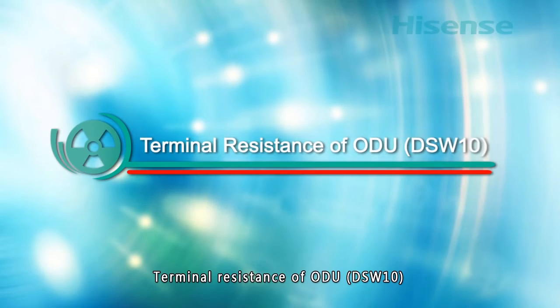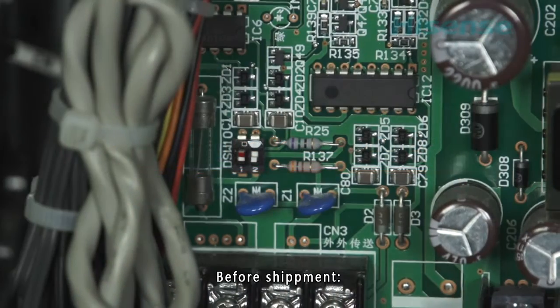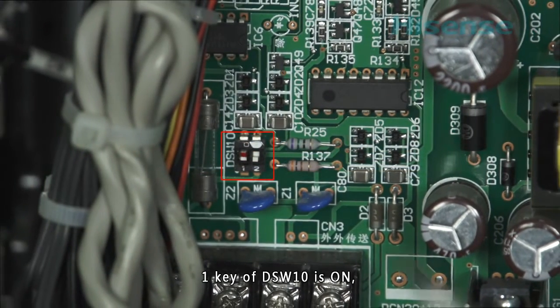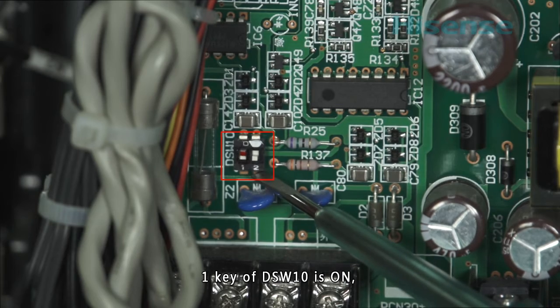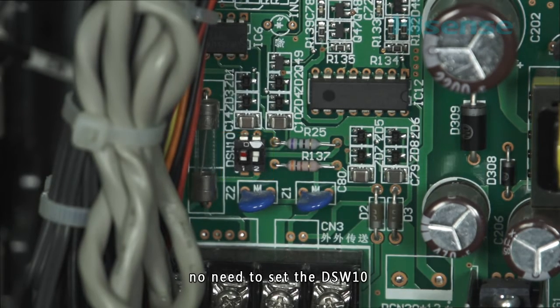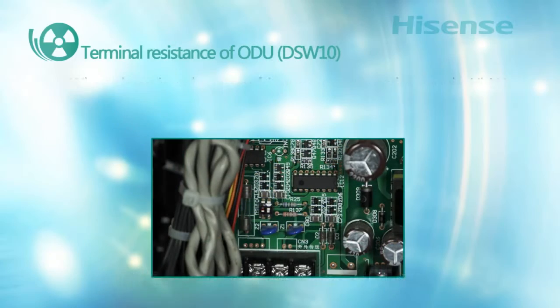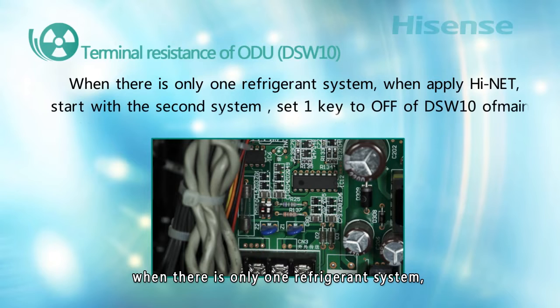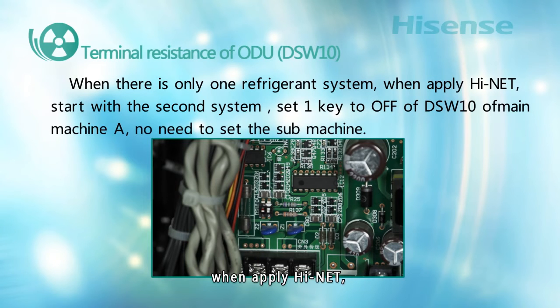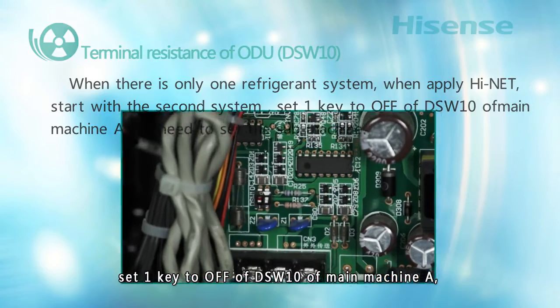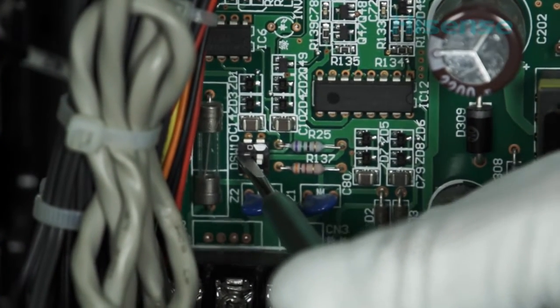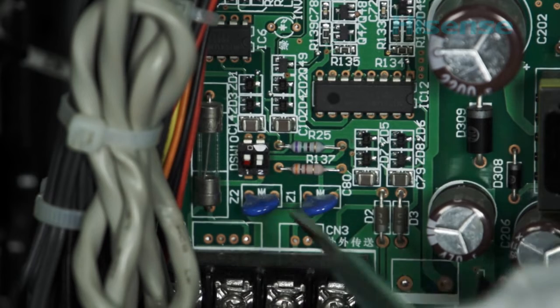Terminal resistance of outdoor unit DSW10. Before shipment, one key of DSW10 is on. No need to set the DSW10 when there is only one refrigerant system. When apply Hi-NET, start with the second system, set one key to off of DSW10 of main machine A. No need to set the sub-machine.